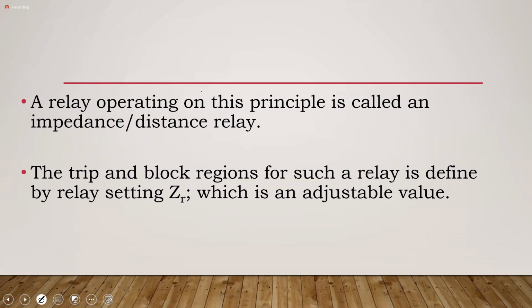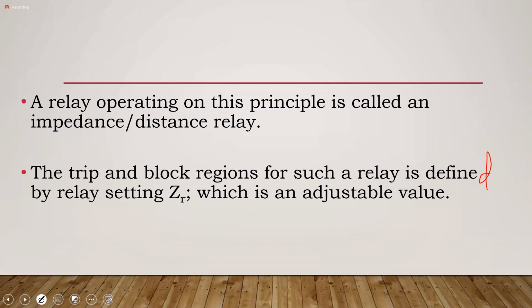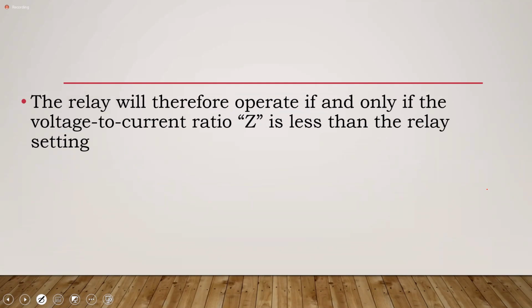Yes. And in terms of the block regions, please just add a D there. Defined by relay setting ZR. And this is based on the positive sequence values for your line. So just like what sometimes we do, we give you quite a bit of information, but of course it is the positive sequence value that you would need to consider. And then the relay will operate if and only if the voltage to current ratio is less than the relay setting. In other words, if Z is less than ZR, where ZR, of course, would be your setting. All right?